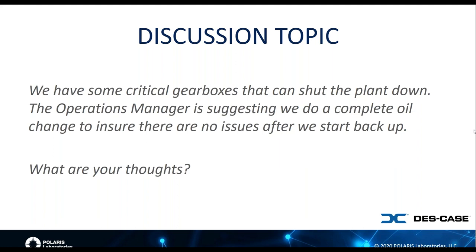So while obviously if the oil's degraded, an oil change is warranted, if you can avoid an oil change, it's always advisable to do so. Not just because of the cost of the oil, but anytime you open up a gearbox or any other asset for that matter, you run the risk of contaminating that asset, contaminating it from the working environment, contaminating it from new oil that perhaps has not been pre-filtered. And so again, anytime you can avoid an oil change, it's always advisable.